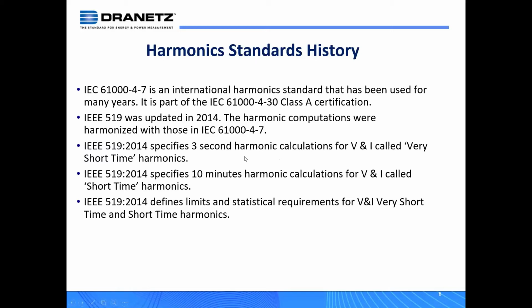What that is, harmonics are evaluated on a 3-second aggregation or calculation. Then there's, I'll call it, a slower parameter called short time harmonics, an aggregation of the very short time into 10-minute harmonic computations. So IEEE 519/2014 added these two parameters, very short time and short time harmonics. And they also defined the limits and the statistical requirements to assess compliance to the requirements in 519/2014.